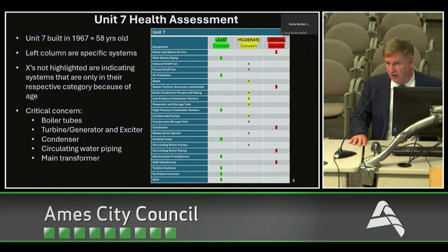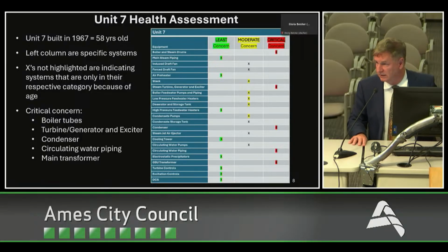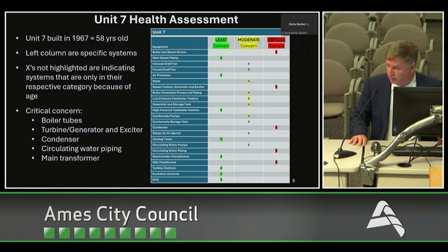As you know, we burn refuse-derived fuel. In the last 5, 6, 7 years, we replaced all those tubes with Inconel-coated tubes. We continue to wear them out, so it's a concern. The turbine generator overhaul itself, an exciter, and maybe I should point out, typically generating units are built for about 30 years. You can push them to 40. We're pushing ours to about 60 years. So the staff is doing a great job maintaining, but it's getting older.